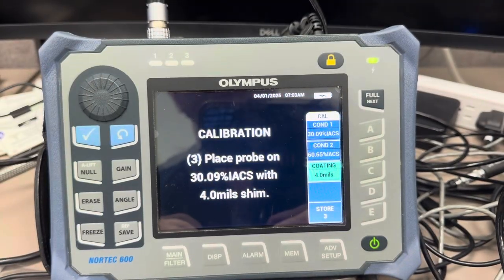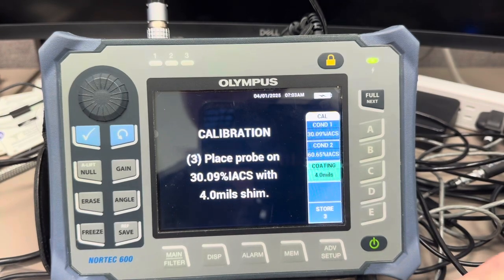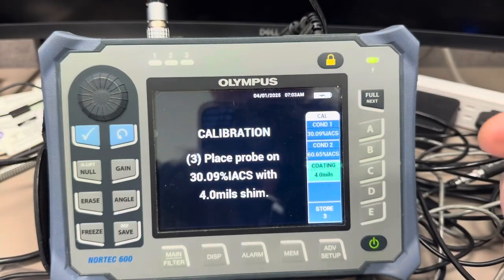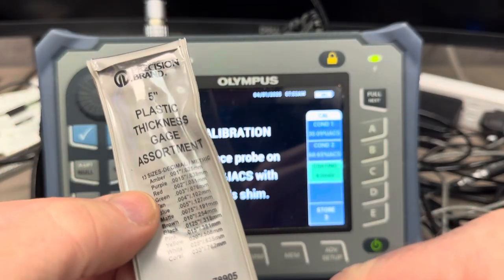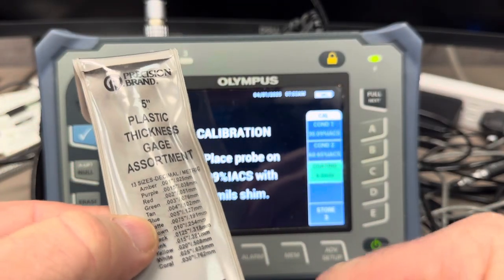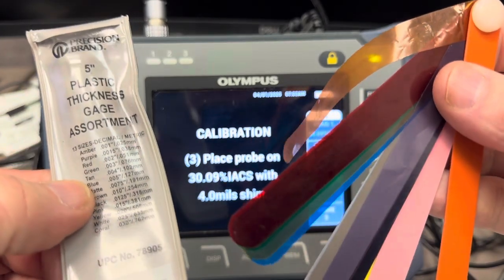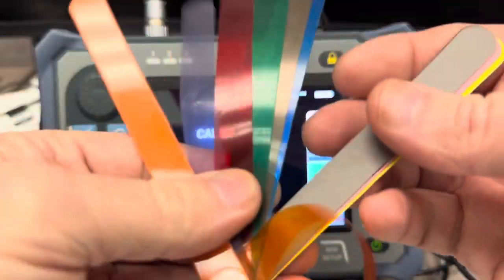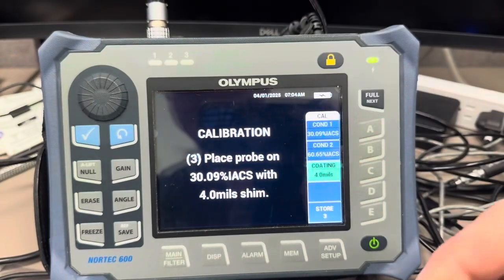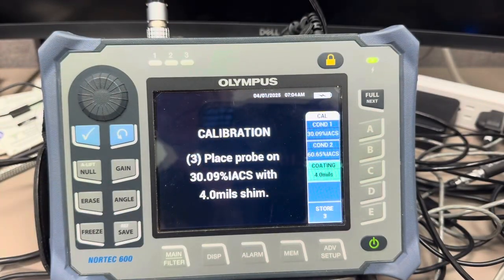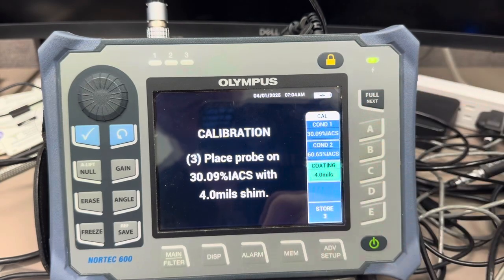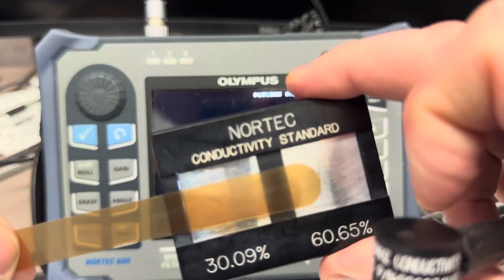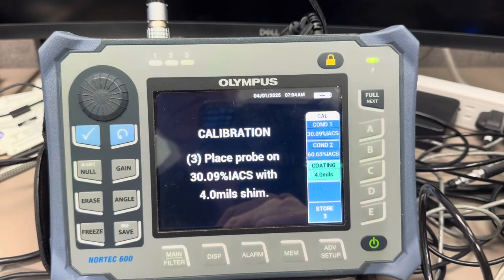Now it says place probe on the 30.09% IACS with the 4 mils shim. So I have to figure out which one that is. So if I look on here, 4 mils is tan. Sometimes it's hard to find these, so I always look at what it's between. So tan is between green and blue. So this is our tan because it's between the green and blue. This is 4 mils thick, or 0.004 inches. So I place that on top of my sample on the left, place the probe on, hit store 3.